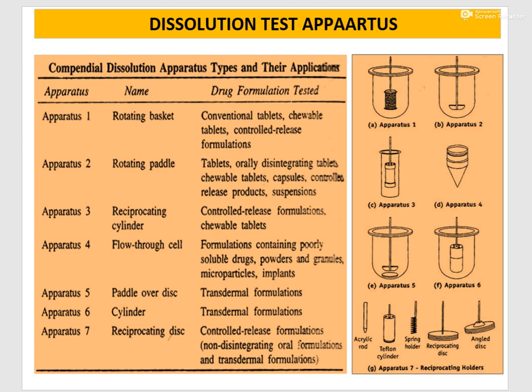This slide depicts various types of dissolution apparatus and their uses. Apparatus 1 is the rotating basket, useful for conventional tablets, chewable tablets, and controlled release formulations. Apparatus 2 is the rotating paddle, useful for tablets, orally disintegrating tablets, chewable tablets, capsules, controlled release products, and suspensions.